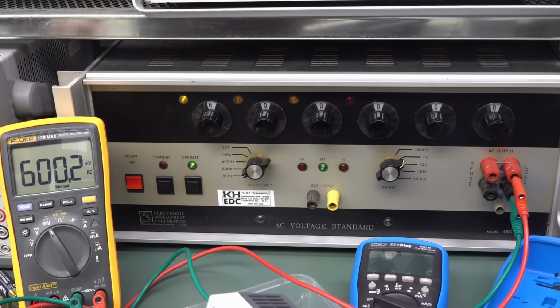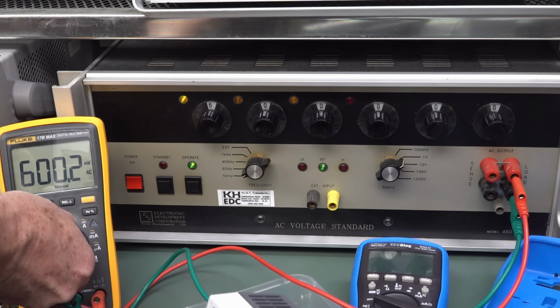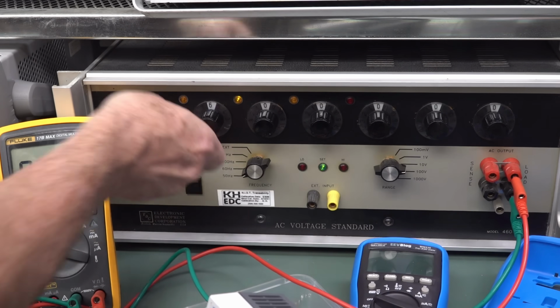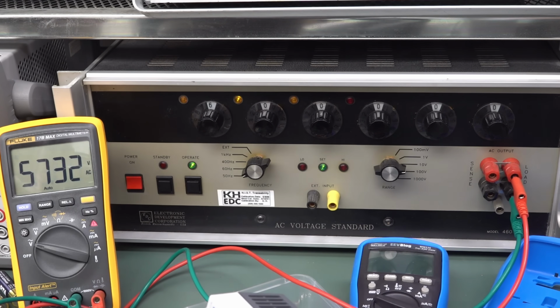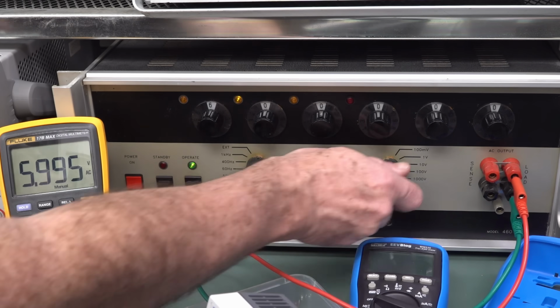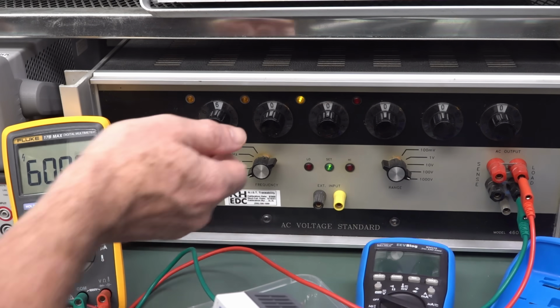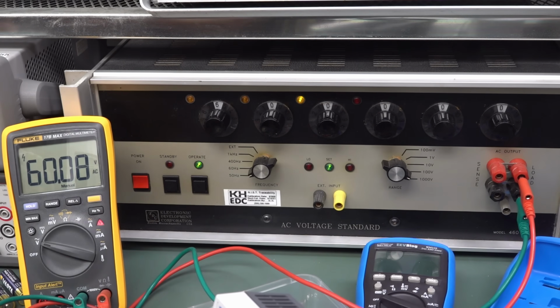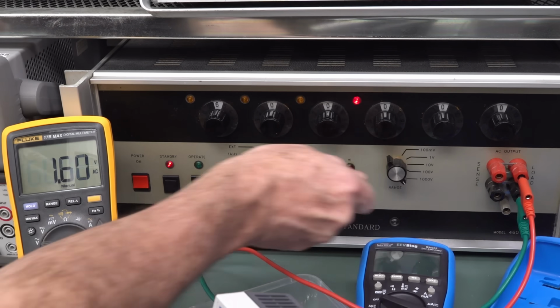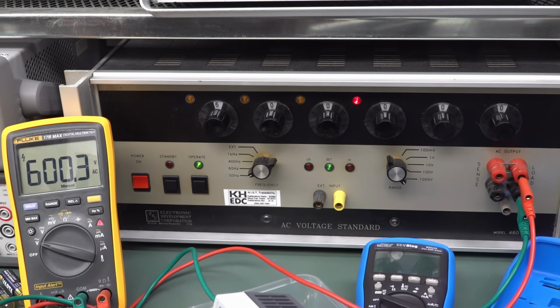And as for AC, I got my AC reference standard here. It's only 0.2 count out, 600 on the millivolt range. That's not too shabby. Turn that to volts, it's the same. We can go up to our 10 volt range here. We'll take a couple of seconds to stabilize. There we go, 5 counts out there at 6 volts. And you've got to remember, this is not true RMS, only average responding, but this puts out a sine wave anyway. There you go, 60 volts. And 600 volts there, no problem.